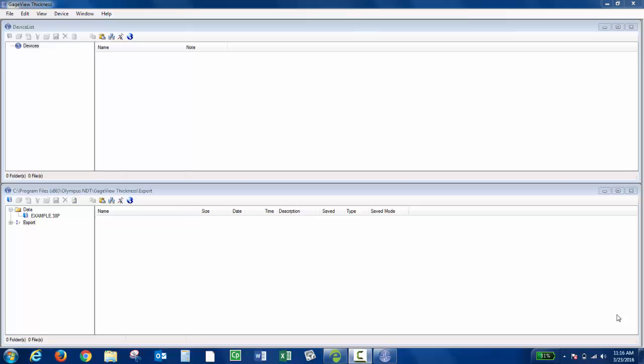You can save custom transducer setups on the 38DLPLUS and 45MG with single element based on your application. What's nice is you can then transfer those setups into GageView. So if you wanted to connect a different instrument that didn't have those setups, you could transfer those custom setups to that new instrument, and it would have the same setups as the previous instrument.